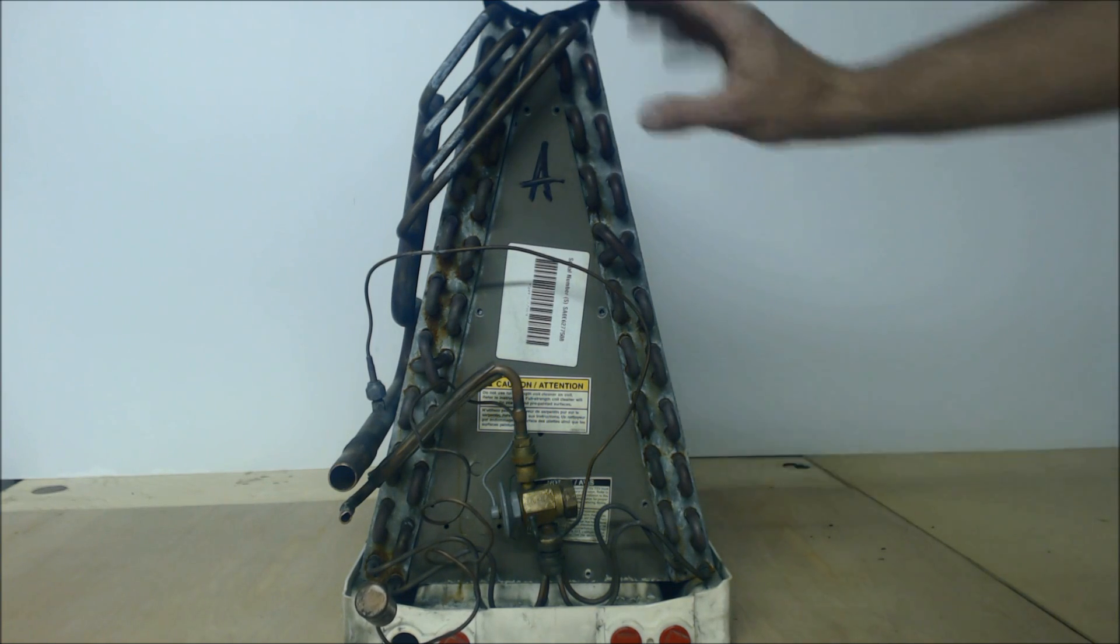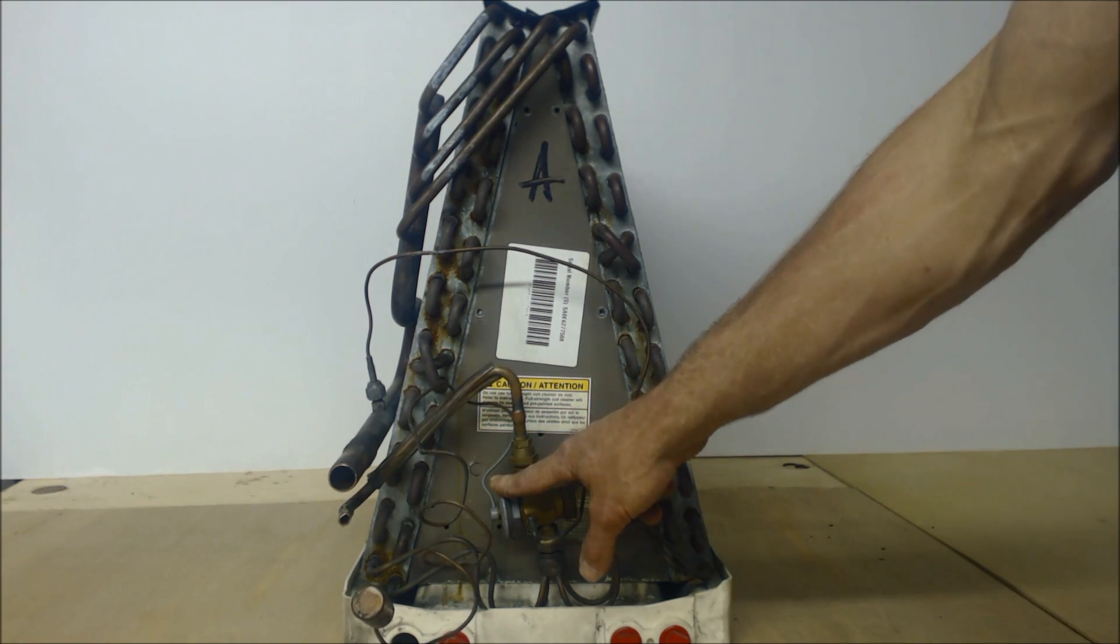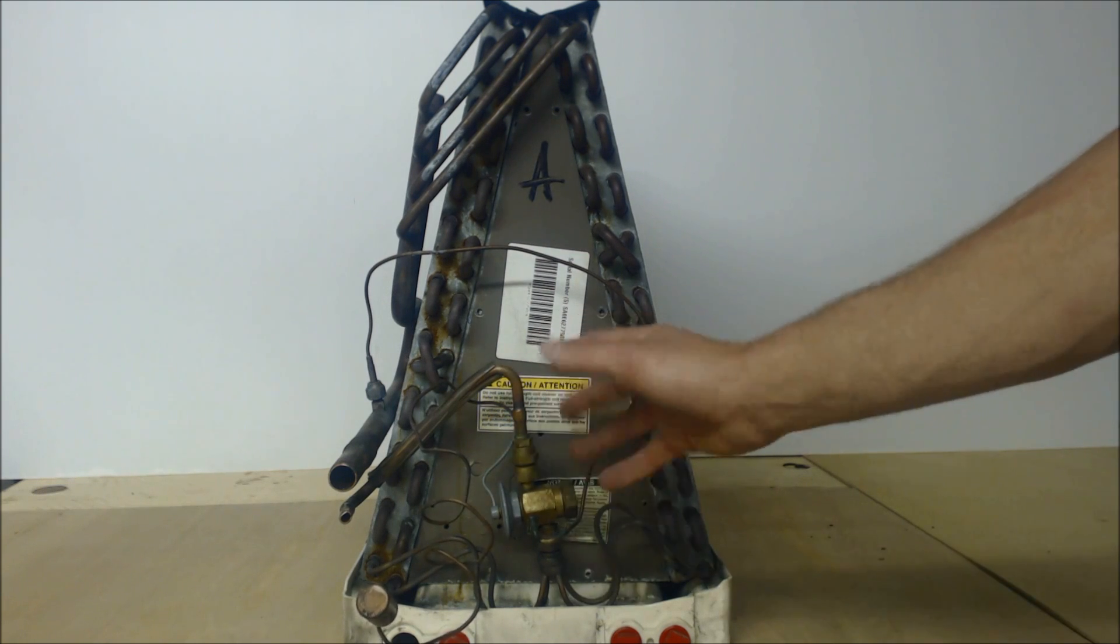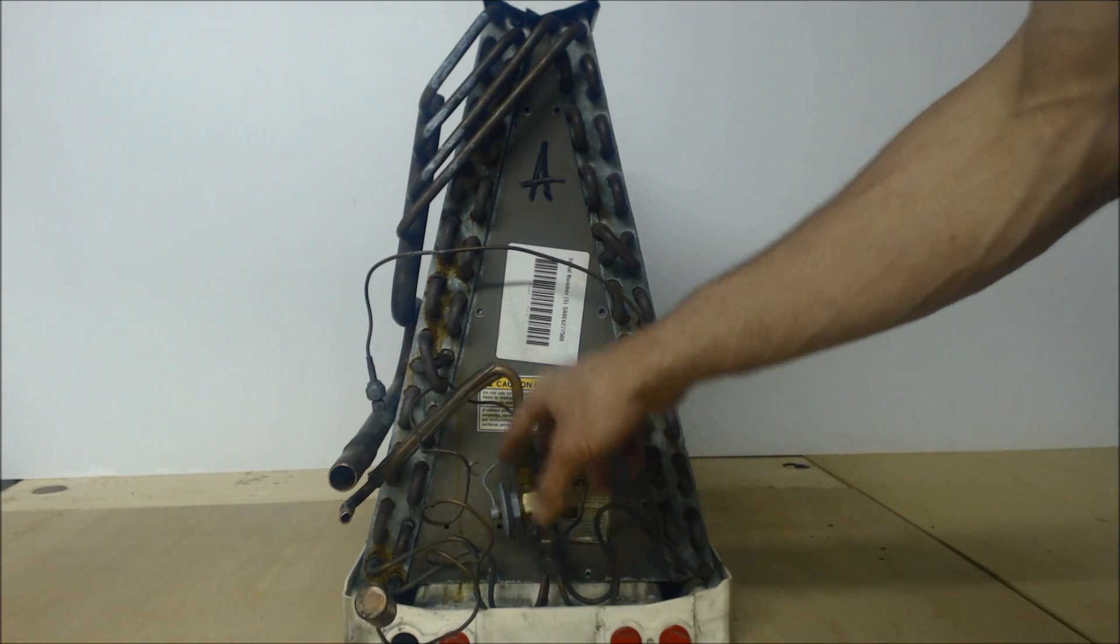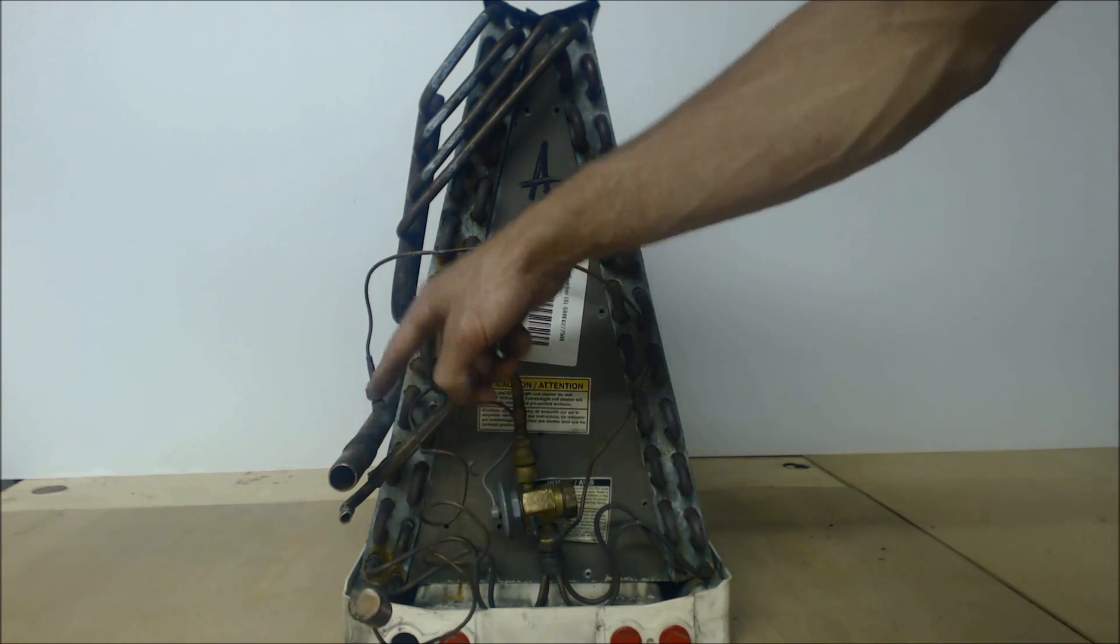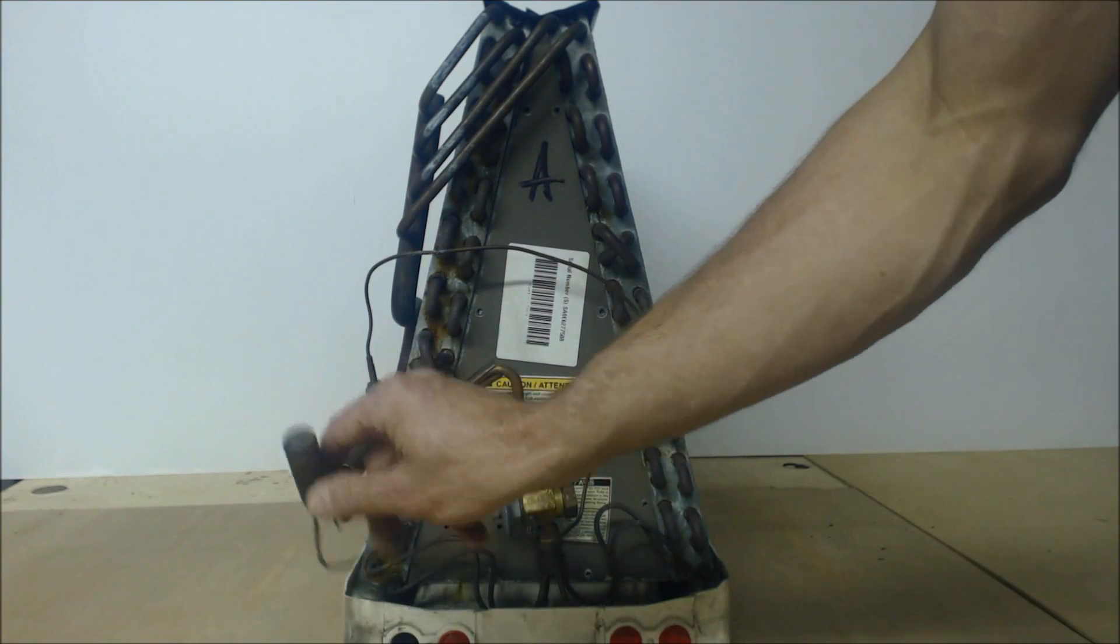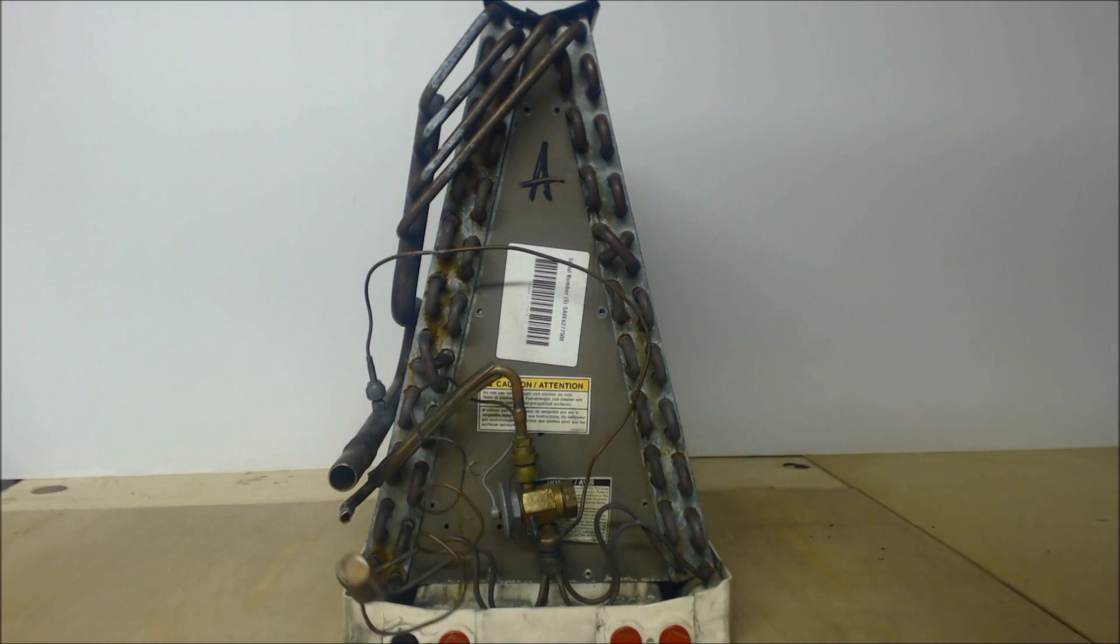The thermostatic expansion valve has more play as far as refrigerant charge goes because it's always trying to maintain 14 degrees of superheat. It reads the pressure right here, and you have a bulb also reading the temperature attached onto the suction line.